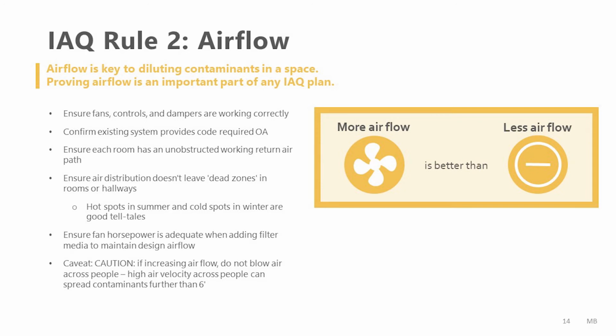I was doing a facility assessment on a building recently where everything checked out. The air handlers were working correctly. Supply diffusers were correctly placed to circulate air. But a piece of furniture, a storage file cabinet, had been placed in front of the return air grill. And then someone had taken some sheets of paper and stored them behind the cabinet. And so the return air grill for the room was completely obstructed. So yes, theoretically, there was a path for the air to enter the room, but if you don't have return air, you're not getting supply air either. Once the door is shut, the room is going to be kind of a dead zone.